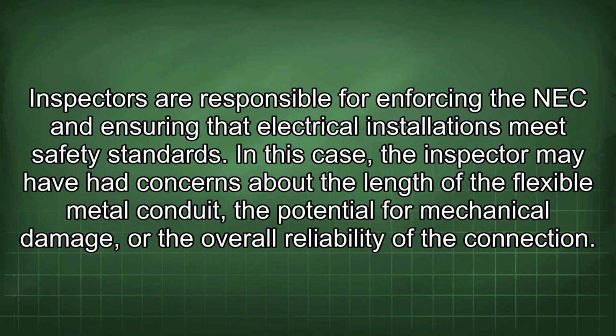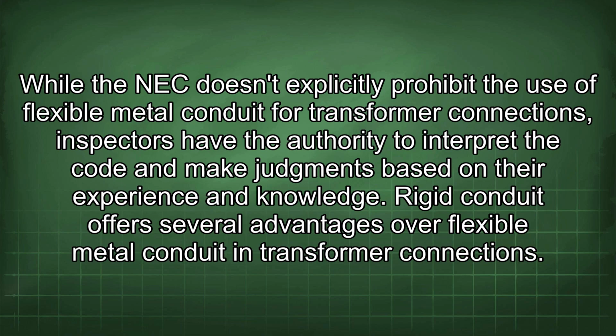Now let's examine the inspector's decision to reject the installation. The inspectors are responsible for enforcing the NEC and ensuring that electrical installations meet safety standards. In this case, the inspector may have had concerns about the length of the flexible metal conduit, the potential for mechanical damage, or the overall reliability of the connection. While the NEC doesn't explicitly prohibit the use of flexible metal conduit for transformer connections, inspectors have the authority to interpret the code and make judgments based on their experience and knowledge.